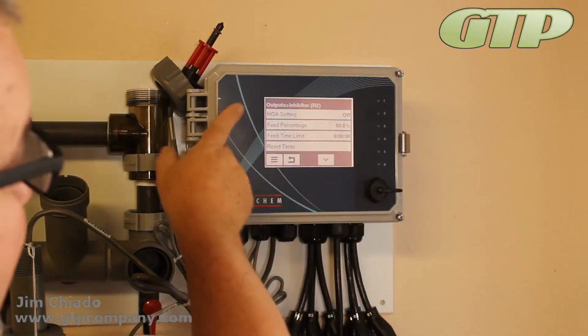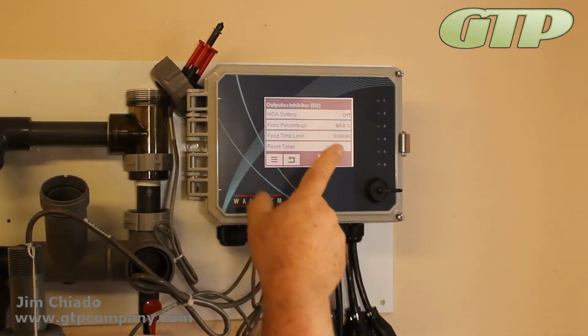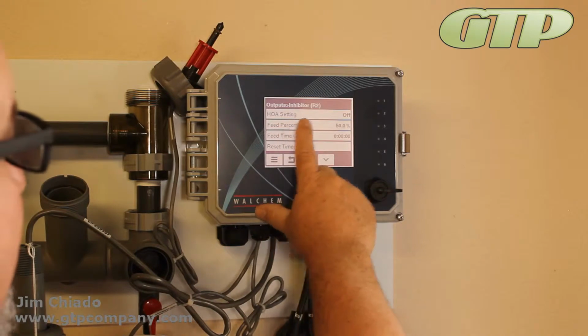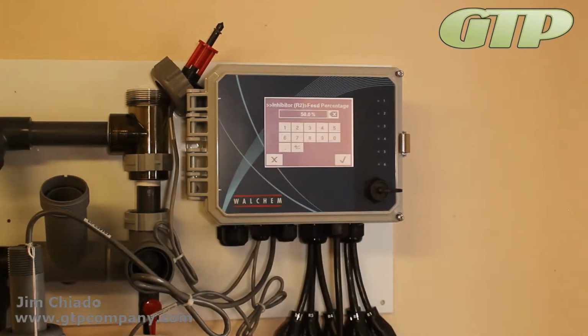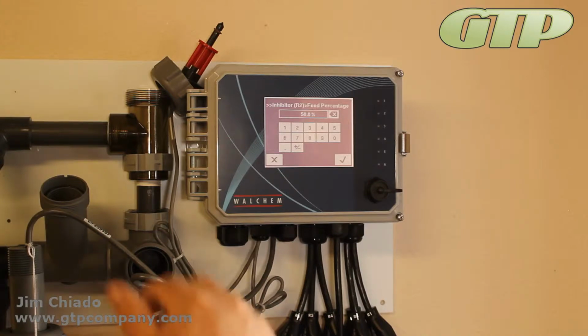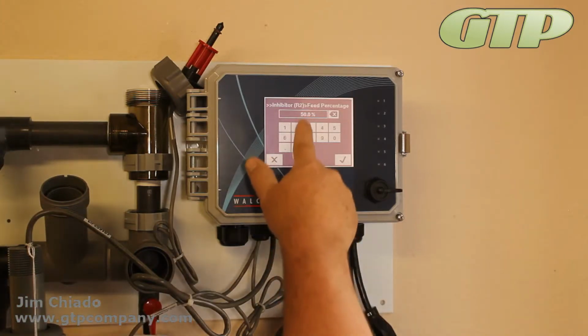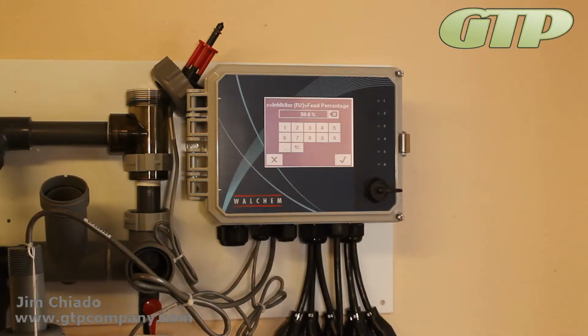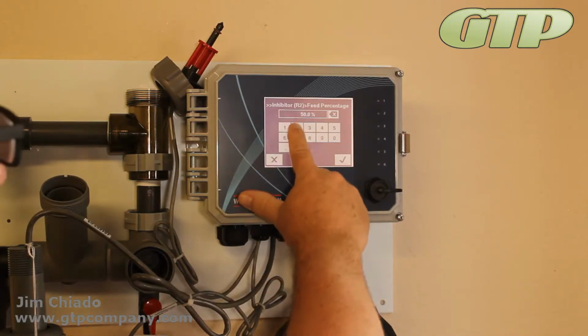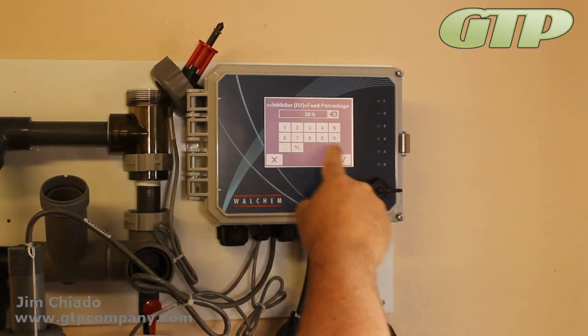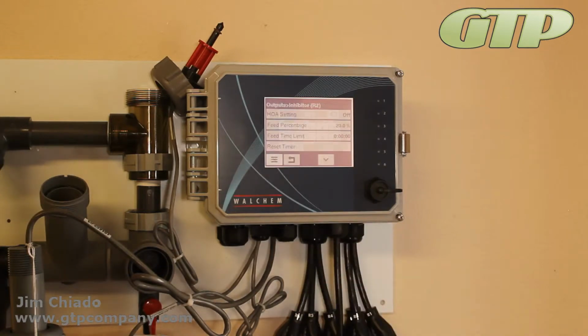Okay, so I'm going to hit the check, and it's going to change the screen display a little bit. Hand-off-auto settings not really necessary because you do have that hand-off-auto menu, but now it has feed percentage, and the feed percentage is based on the amount of bleed time. If it bleeds for an hour, 50%, 30 minutes it's going to feed. So 50% may be a little high for you. You guys may want to change it to like 20%. Just type in your percentage and hit the check.